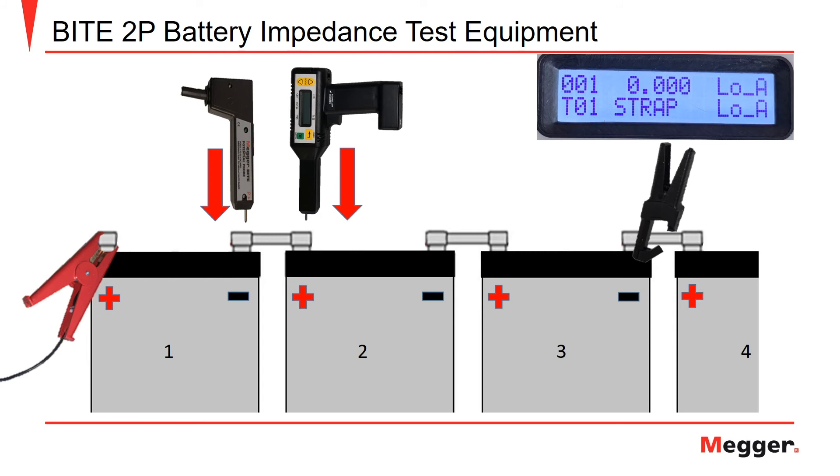Just as for the voltage and impedance measurements, to record the intercell resistance measurements, you will apply the pistol grips in the same manner. However, the receiver pistol will be applied to the positive post of the following battery in the string. In this case, the potential probe is applied to the negative post of battery number one and the receiver pistol is applied to the positive post of cell number two to measure the strap between those two cells. When the strap resistance reading is displayed, pull the trigger on the receiver to save the value.